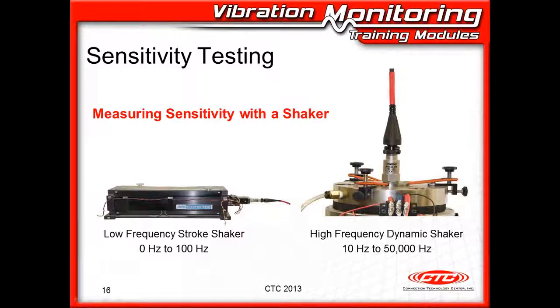If we're testing the sensitivity of an accelerometer, or we want to check the calibration really, well, if we're working on very low frequencies, maybe I've got a wind turbine and I want to know what the frequency is at 1 hertz, I need a stroke shaker. And this is just like a hydraulic cylinder. And it strokes back and forth at a predetermined rate and amplitude. It also has a reference accelerometer mounted in it. So you can see our accelerometer will be mounted here, and it would be compared to the reference accelerometer in this head piece right here. And this is good for 0 hertz DC all the way to 100 hertz.